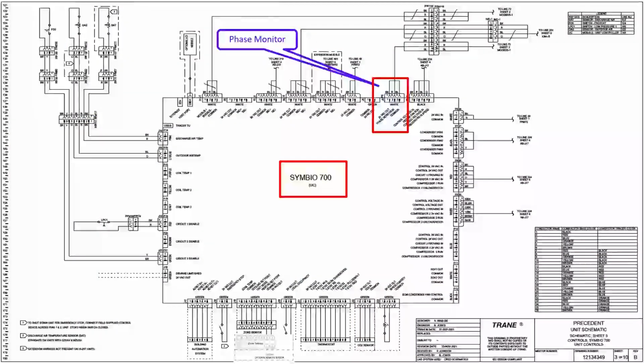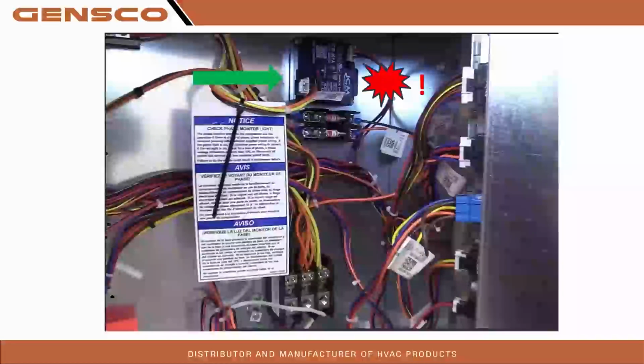There's your phase monitor. I'll show you a picture of that. Green is good, red is bad. It's pretty simple. Phase monitor, so you just want to swap two of those legs, two of the three legs, and you should be up and running. But again, green flash is good, red means you need to swap those phases. And here's another good picture of that hinge panel.